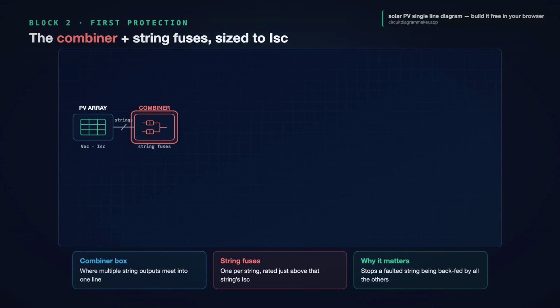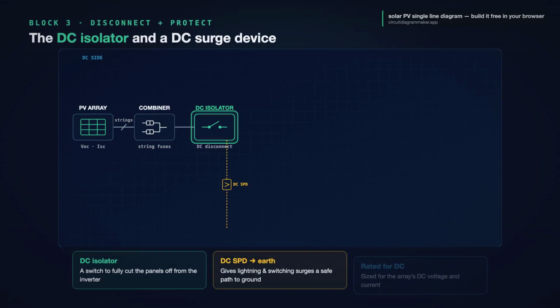Block 3, the DC isolator and a surge protection device. The DC isolator, sometimes called the DC disconnect, is a switch on the DC side that lets you completely cut the panels off from the inverter. It is there so anyone working on the system can make it safe. On the diagram, it is a switch symbol, rated for the array's DC voltage and current.